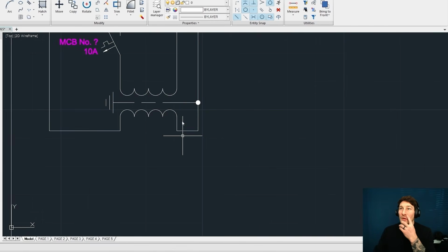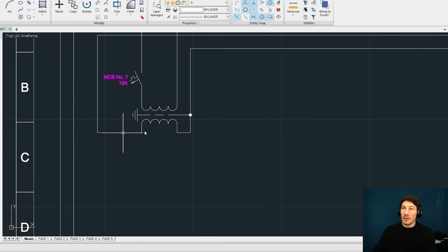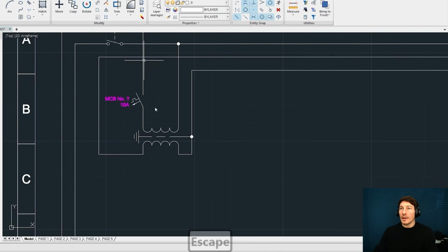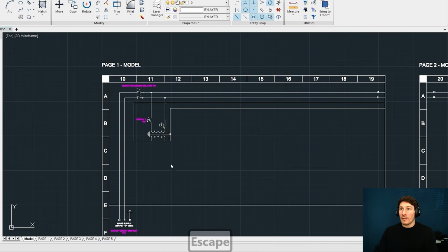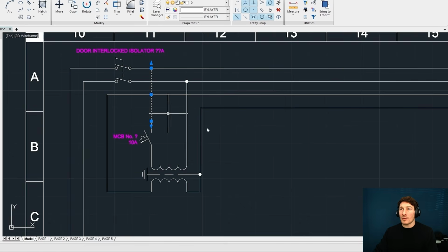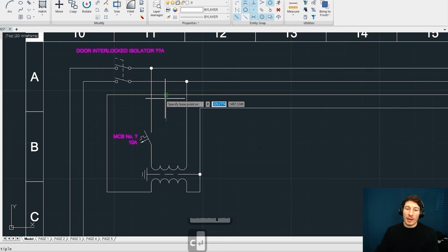And what we want to do on the 0 side is earth it. We want to connect it to protective earth. So that's what I've done here. You can see that there's an earth connected to the transformer, so we want to connect that earth to the 0 volts as well. And what that does is it removes any potential differences, especially when we're dealing with controls, sensitive signals and stuff.